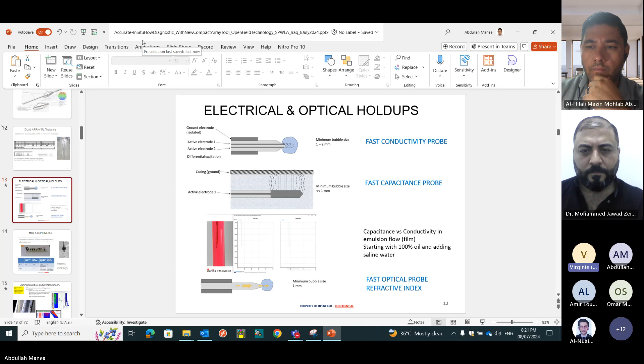We are able to have this fine resolution optics. I must say there is one case where we cannot discriminate oil versus water. When oil is very light and water is very saline, the refractive index of both is very close. So that's down to the physics. In that case, we cannot discriminate oil versus water.